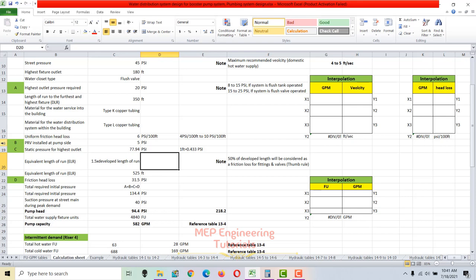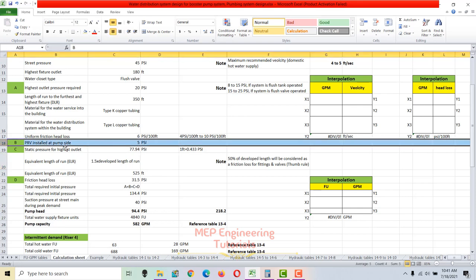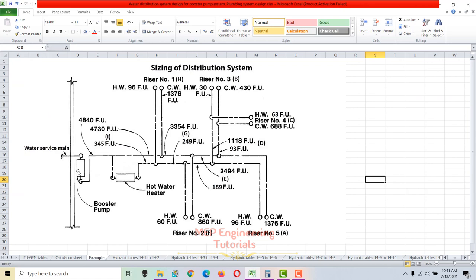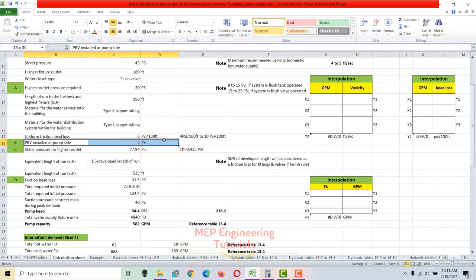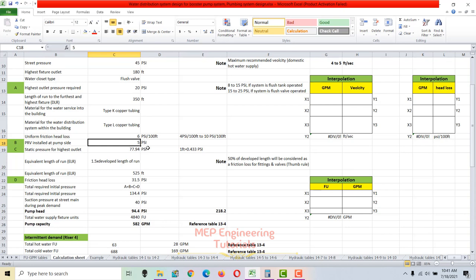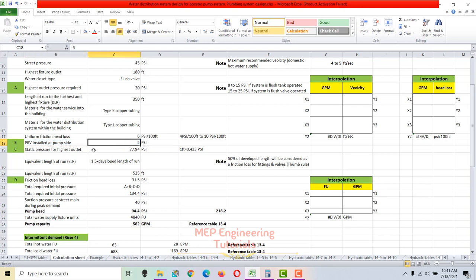At the pump side, a PRV is installed along with other fittings such as a drain cock and a water meter. I've added the PRV pressure loss — obtained from the manufacturer — as 5 psi, and we need to add the water meter head loss here as well.